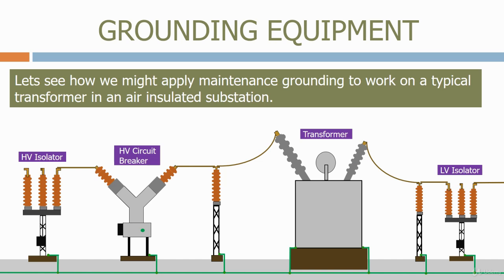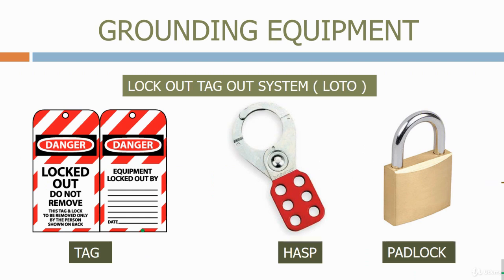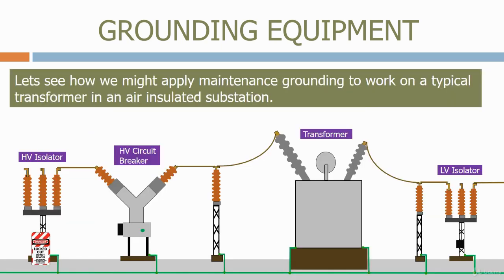When the high voltage isolator is fully open, it's physically locked out using a padlock. We then apply a lockout tag to warn people not to try and operate the isolator. This procedure is called a lockout tag-out system and consists of tags and hasps and padlocks to lock out the equipment and make sure it can't be operated. We then do the same on the low voltage isolator. The transformer is now electrically isolated from the system.